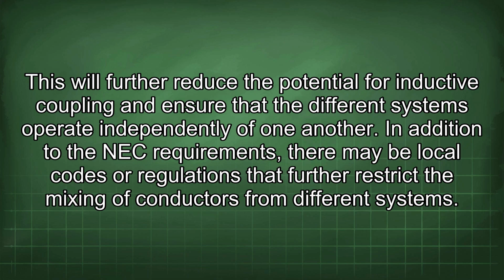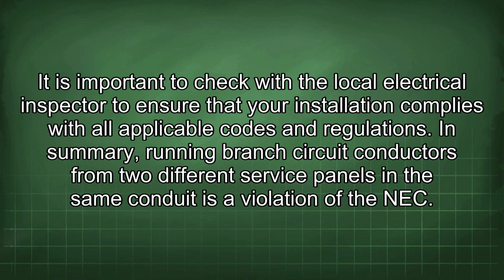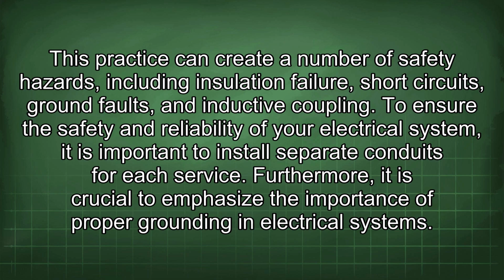In addition to the NEC requirements, there may be local codes or regulations that further restrict the mixing of conductors from different systems. It is important to check with the local electrical inspector to ensure that your installation complies with all applicable codes and regulations. In summary, running branch circuit conductors from two different service panels in the same conduit is a violation of the NEC. This practice can create a number of safety hazards, including insulation failure, short circuits, ground faults, and inductive coupling. To ensure the safety and reliability of your electrical system, it is important to install separate conduits for each service.